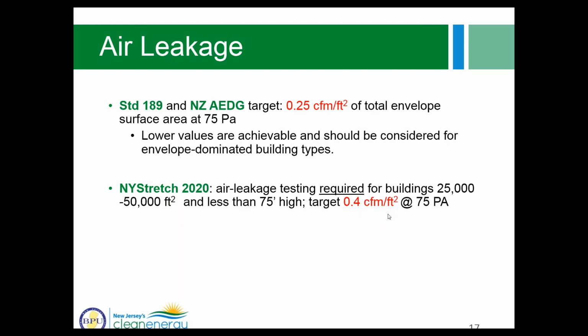And this is an opportunity for you to claim performance credit with P4P, because if the building performs air leakage testing, you can model leakage rate based on the testing in the proposed design, and any savings associated with air leakage reduction directly contribute to your incentive tier. The Standard 189 and Net Zero Advanced Energy Design Guide target is 0.25 CFM per square foot at 75 Pascal.